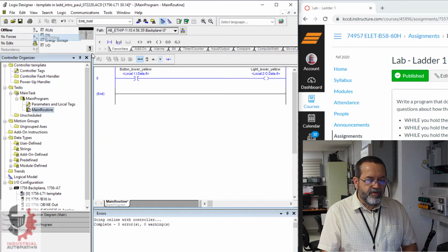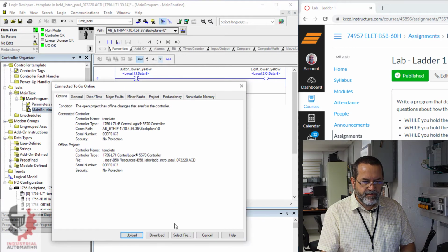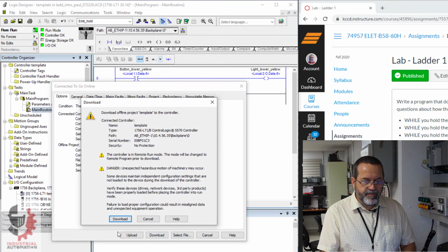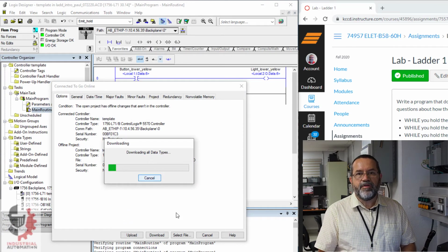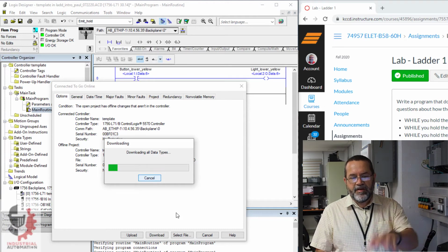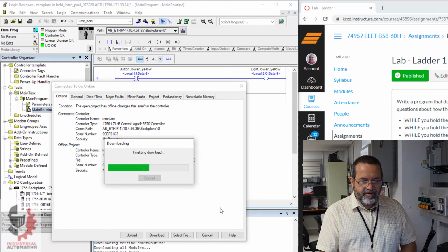All right, I'm going to go online with that. Download it. Always download, don't upload. If you upload, you're going to take whatever's in the PLC and you're going to overwrite what you have in Studio 5000. And generally, that's not what you want to do.